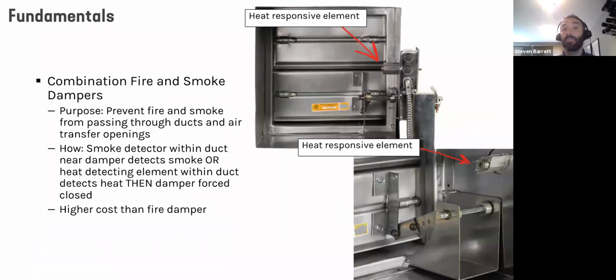Then finally, a combination fire and smoke damper is just what it sounds like. It's a combination of the two. So it both prevents fire and smoke from passing through. And really the difference is that it has both means of detection. So it's typically a heat responsive element that would detect the temperature, also a smoke detector. And if either one of these detect heat or smoke, then the damper is force closed with the actuator. So again, these are higher cost than a fire damper.